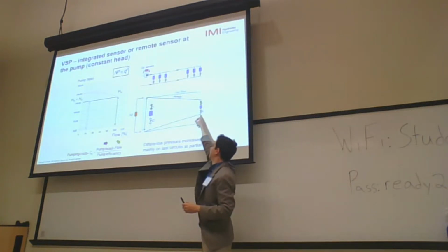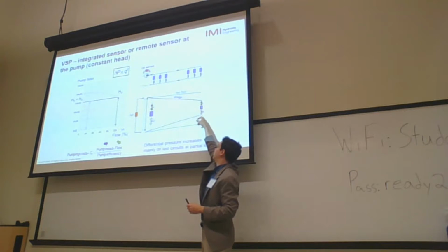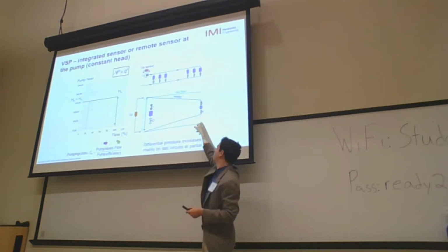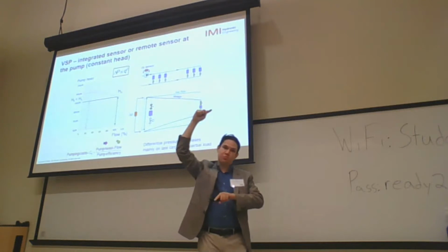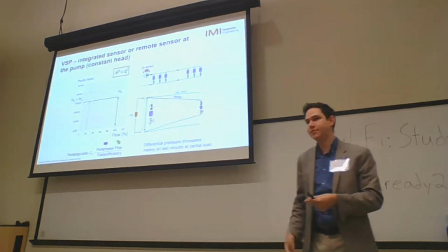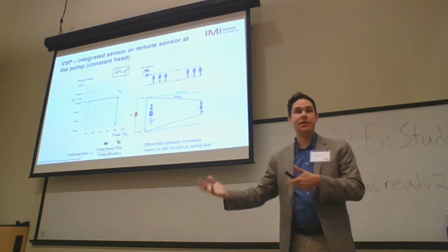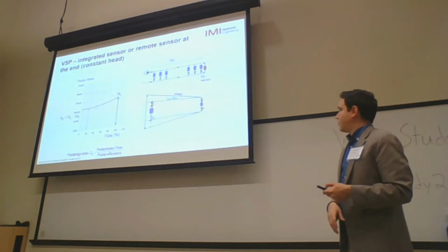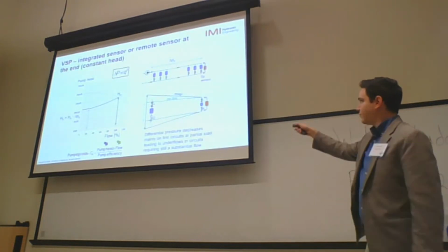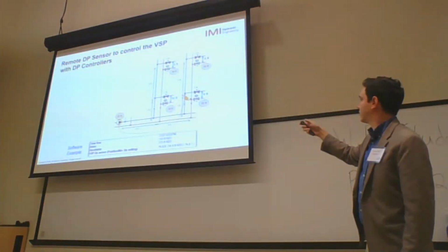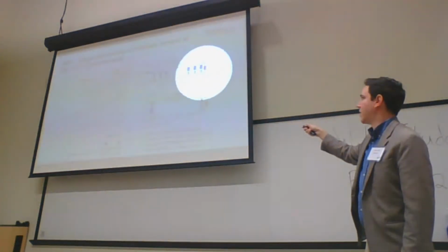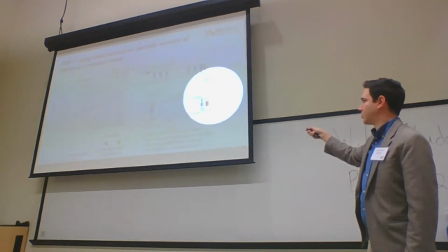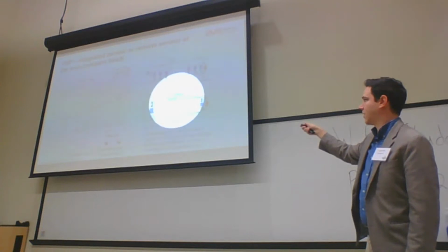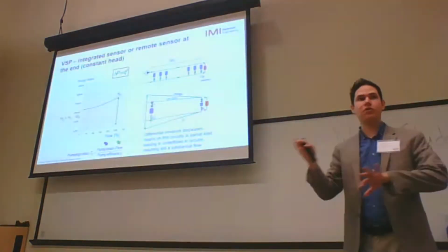So my index coil only needs pressure between the two black lines, but it's getting pressure between the two green lines. So it's getting a much higher differential pressure than it actually needs. And that's why it's a waste of energy placing the DP sensor at the pump. If you place a DP sensor at your index coil, here I have the example. My DP sensor is right there in my index coil. At a low flow condition, you see these two green lines right here. That is what it's getting for my whole installation.